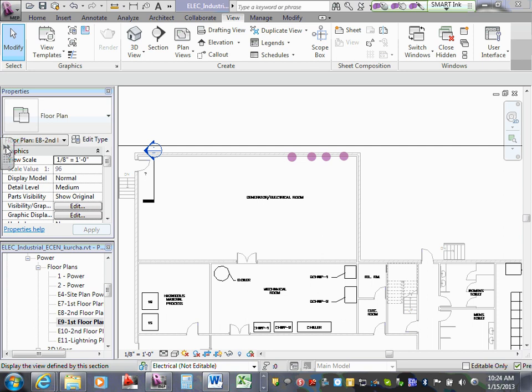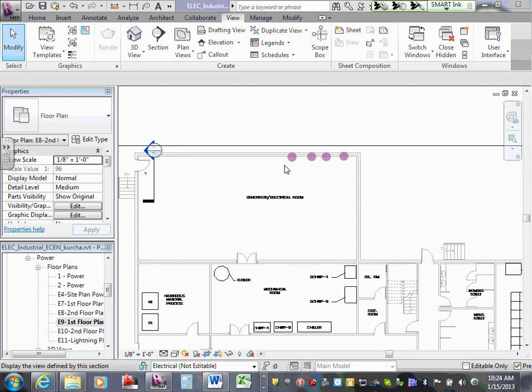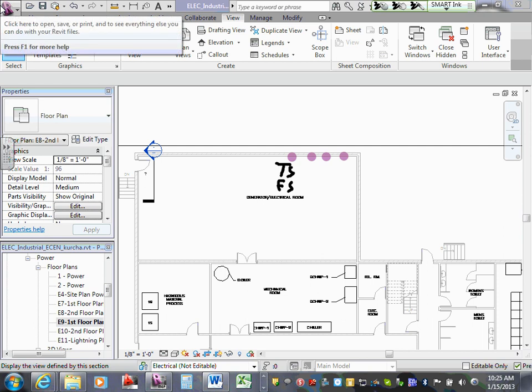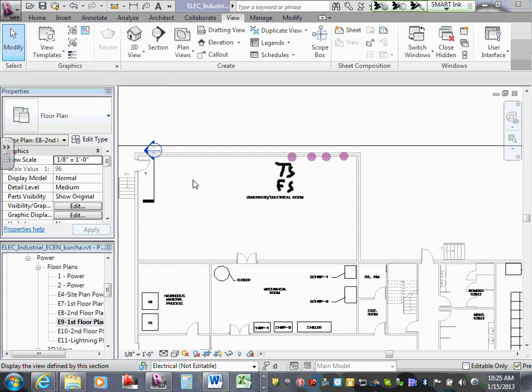Yeah, typically when they're doing the risers, they're gonna use dual monitor modules. It's just 2 modules in one box, so you don't have to have all separate. That would be the tamper switch and flow switch for each one. Is that what you mean? Okay. Like we did in the commercial ones, every zone is gonna have a tamper and a flow switch. We'll have 4 zones for a total of 8 devices. Yep, you got the manufacturing first floor, computer room pre-action, the balance of the first floor and the second floor.